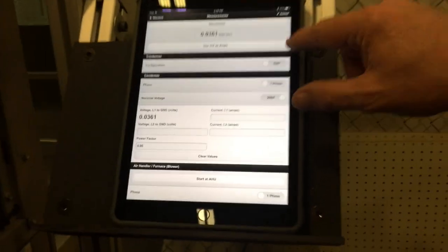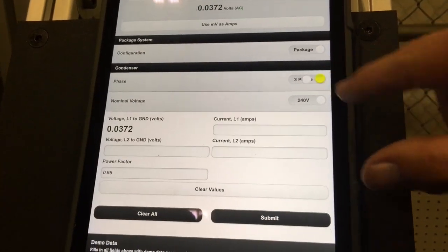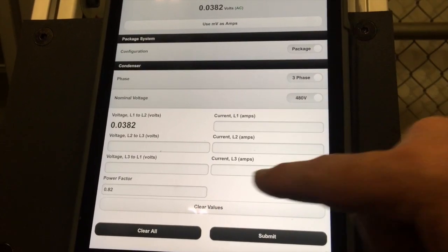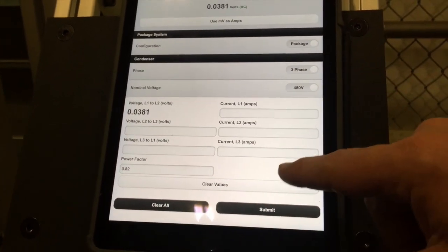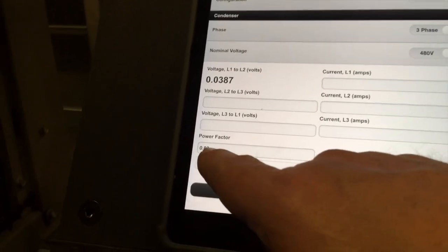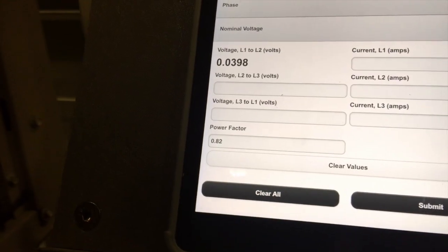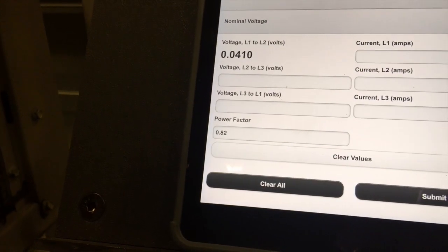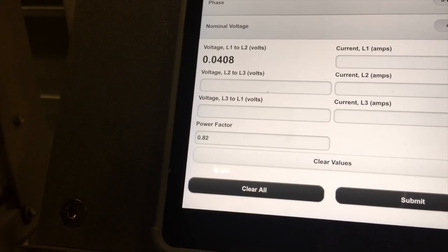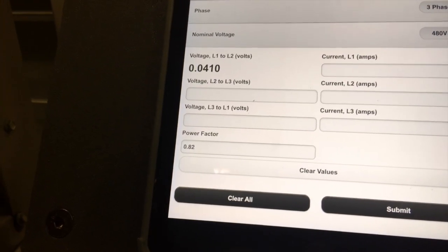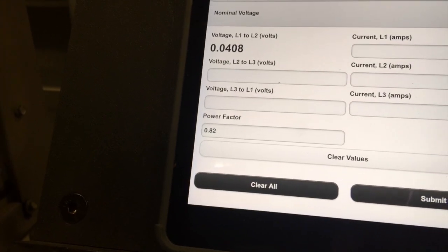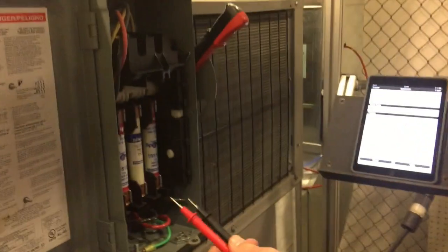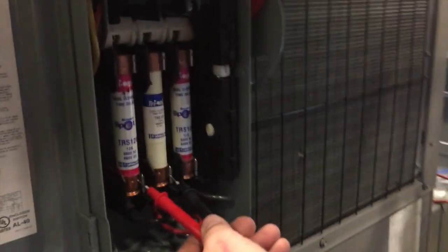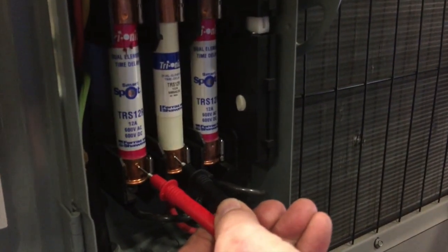The one thing we have to do here is this is a package system. It is 3-phase and it is 480 volt. So you can see now we have all our fields put in. Our power factor in this case is always a typical power factor. If you have a meter that actually measures power factor, you can put that in here. In this case, we don't, so we're going to leave the typical power factor number in. So we're going to go ahead and we're going to measure from L1 to L2.